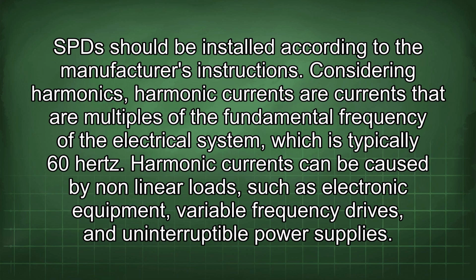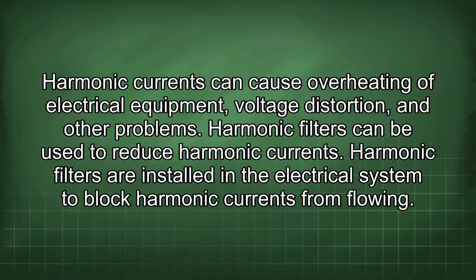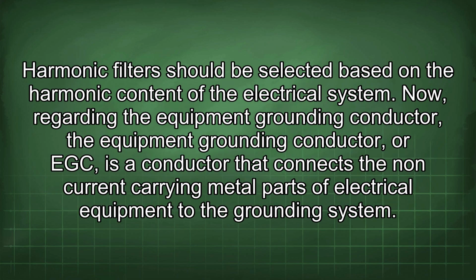Considering harmonics, harmonic currents are currents that are multiples of the fundamental frequency of the electrical system, which is typically 60 Hz. Harmonic currents can be caused by nonlinear loads such as electronic equipment, variable frequency drives, and uninterruptible power supplies. Harmonic currents can cause overheating of electrical equipment, voltage distortion, and other problems. Harmonic filters can be used to reduce harmonic currents. Harmonic filters are installed in the electrical system to block harmonic currents from flowing. Harmonic filters should be selected based on the harmonic content of the electrical system.